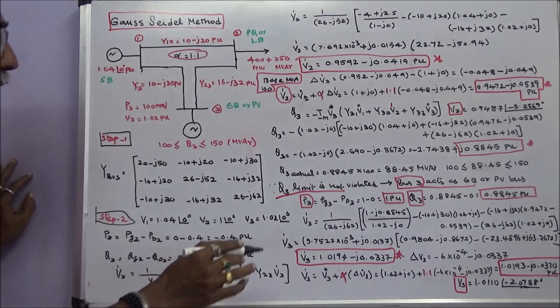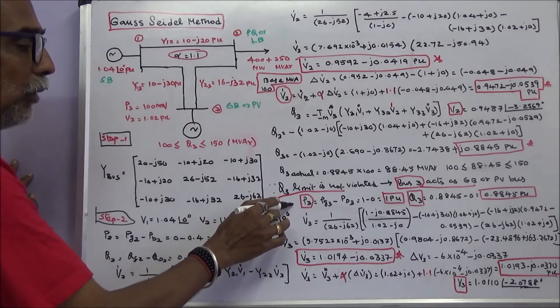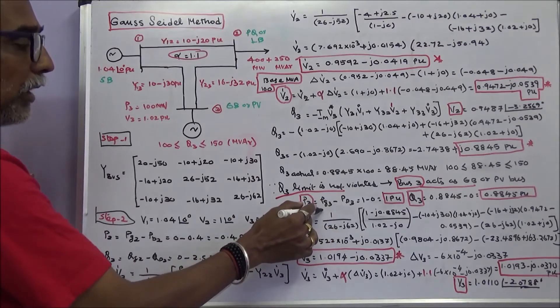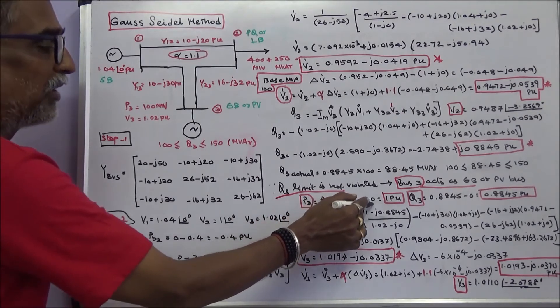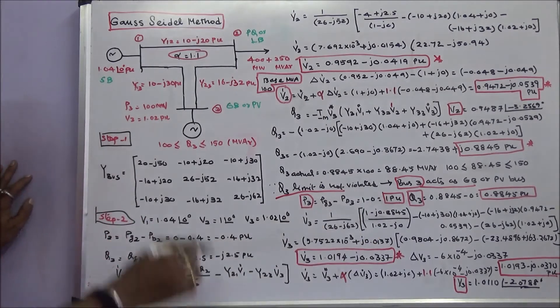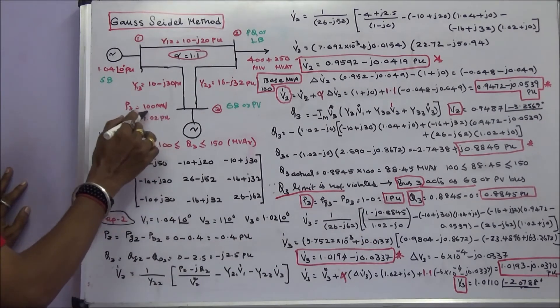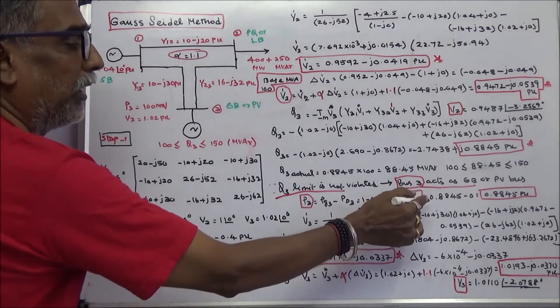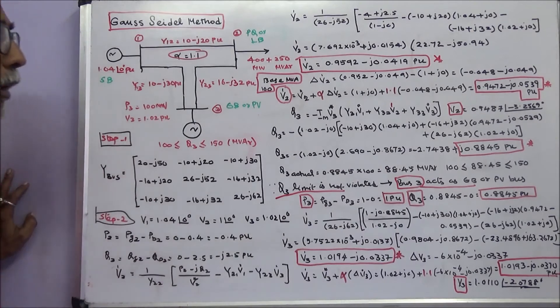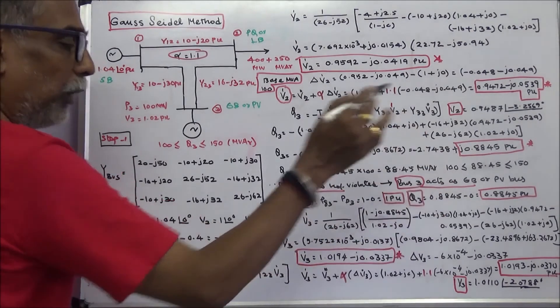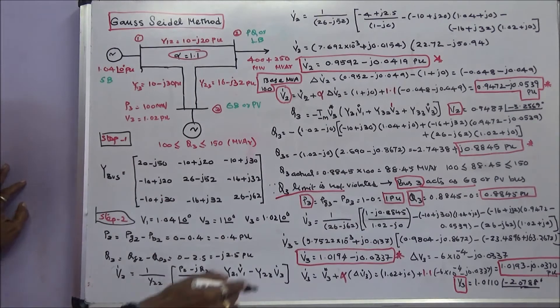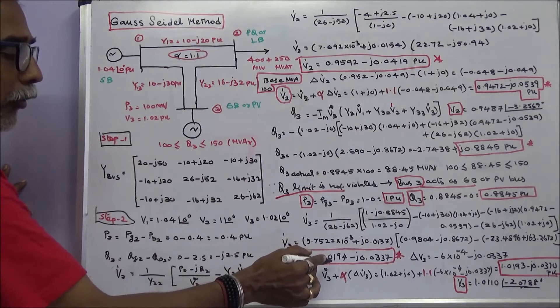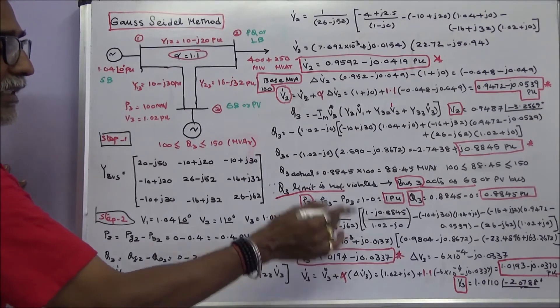Now we calculate P3. P3 = PG3 − PD3 = 1 − 0 = 1 per unit, since P3 is 100 MW and base is 100 MVA. Q3 = 0.8845 − 0 = 0.8845 per unit. Now we can calculate V3, which gives V3 = 1.0194 − j0.0337 per unit.